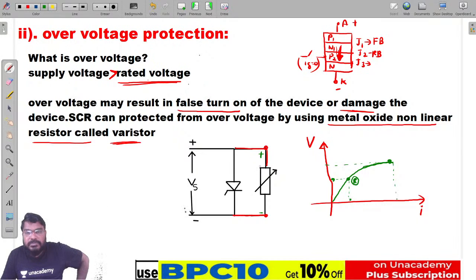For low voltage it offers the same small amount of voltage across the device. For high voltage, the varistor can reduce this over voltage because of its non-linear characteristic. That's why the varistor is connected across the anode to cathode terminal of the SCR as shown in the figure, to protect the SCR from over voltage.